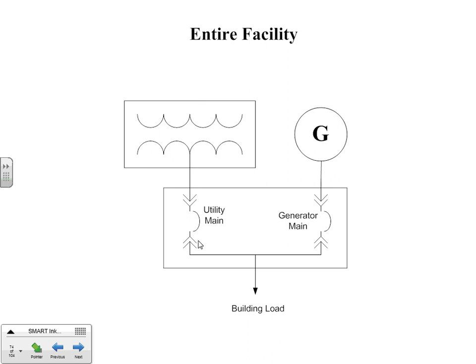Power comes in through the utility main, feeds the load. In a curtailment period, power is still here, but we start the generator set, synchronize with the utility, close this breaker. The load doesn't know anything happened. The utility main opens, and the utility can now use that power that was feeding this facility elsewhere, instead of wheeling in power from another source additionally.